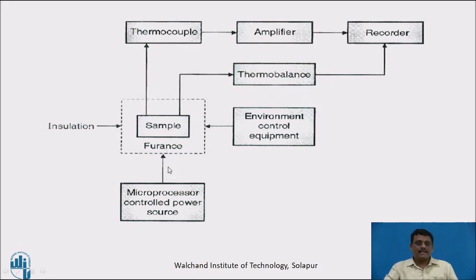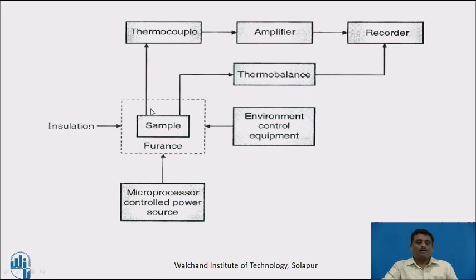The furnace is connected with a microprocessor-controlled power source, which is capable of heating the sample at a controlled rate — minimally 2 degrees centigrade per minute up to 250 degrees centigrade per minute. The furnace is also connected with a thermocouple and a thermobalance. When the sample is being heated, some signals are received by the thermocouple and some by the thermobalance.